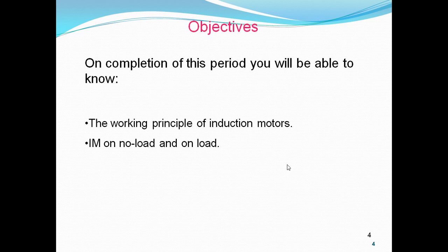The three finishing windings are brought out and connected to one side of the slip rings. On the other side, brushes are kept. The three brushes are connected to a three-phase star-connected external rheostat. So by using these brushes, we can connect some external resistance in series with the rotor winding during the starting period.